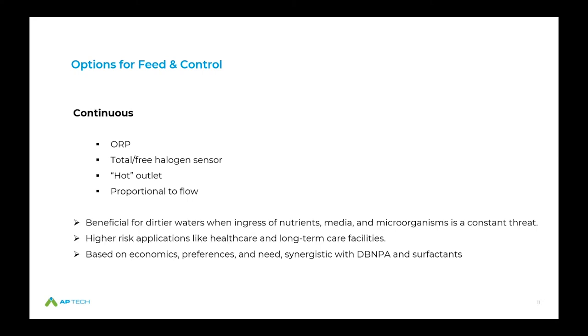Reasons to go continuous include dirtier waters with constant ingress of nutrients, media, and microorganisms. In clean water systems, there's also no reason you couldn't use continuous feed. Higher risk applications — considering healthcare and long-term care facilities — now have ever-expanding oversight with water management plans and ASHRAE 188, where continuous feed would be beneficial or desired. Economics, personal preferences, and synergistic use coupling with DBNPA and surfactants also support continuous feed.